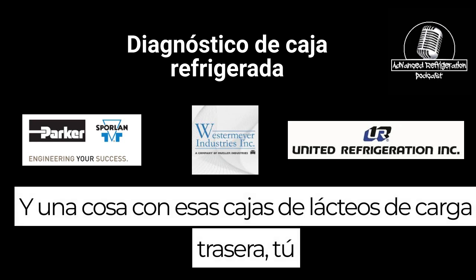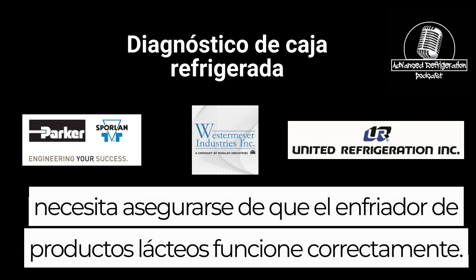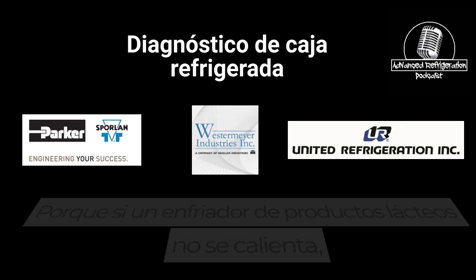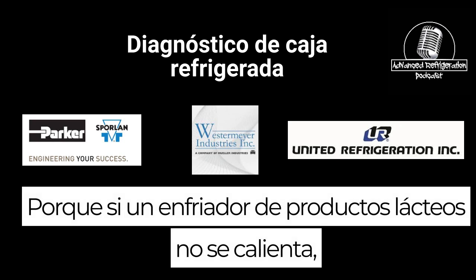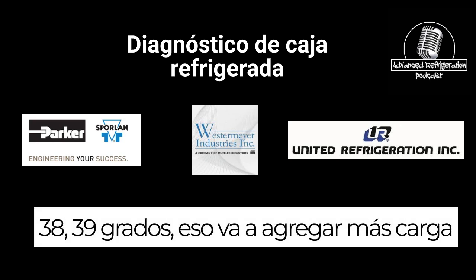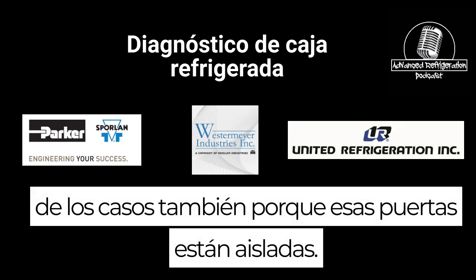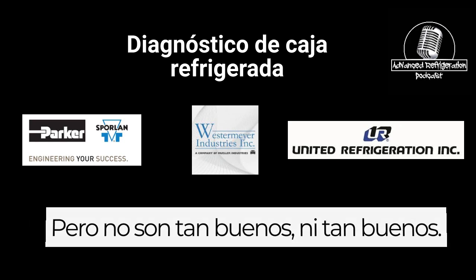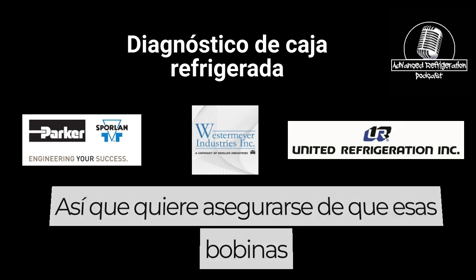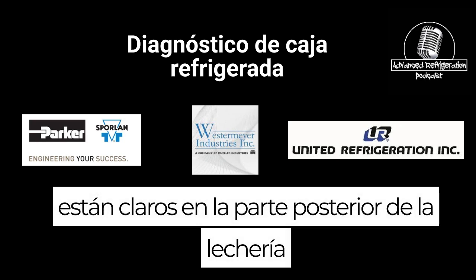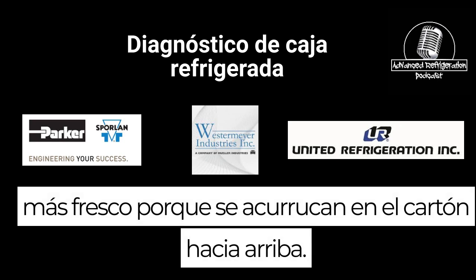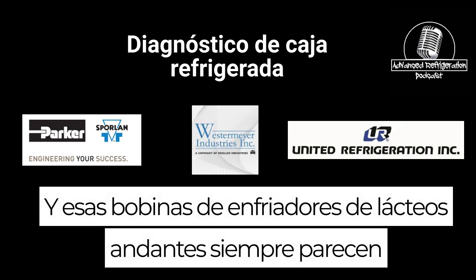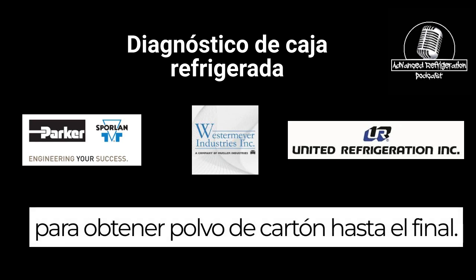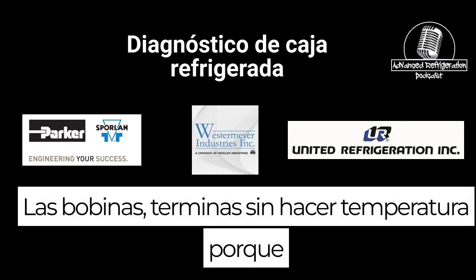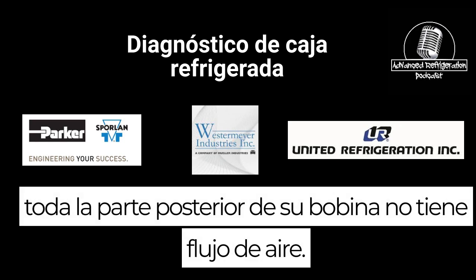And one thing with those rear load dairy cases, you need to make sure the dairy cooler is working properly. Because if a dairy cooler's running warm, 38, 39 degrees, I mean, that's going to add more load to the cases too, because those doors are insulated, but they're not that great. So you want to make sure those coils are clear on the back of the dairy cooler, because in those walk-in dairy coolers the coils always seem to get cardboard dust all over the back of the coils. You end up not making temperature because the whole back of your coil has no airflow.